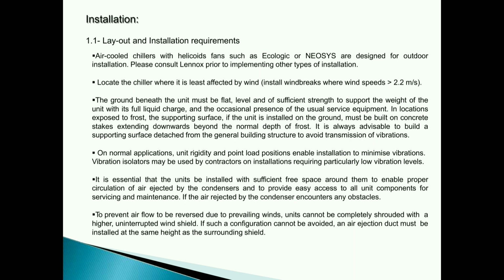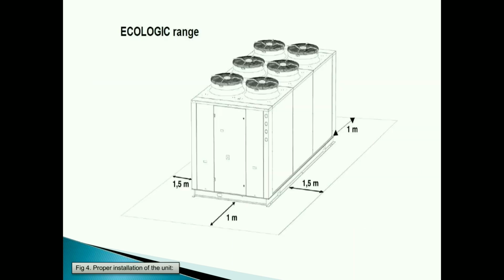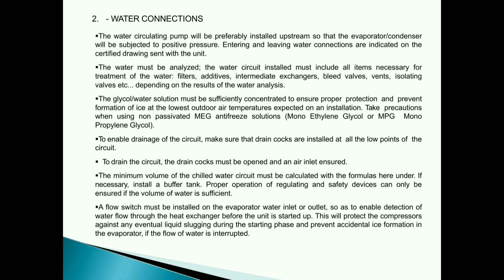It is essential that the units be installed with sufficient free space around them to enable proper circulation of air ejected by the condensers and to provide easy access to all unit components for servicing and maintenance. If the air rejected by the condenser encounters any obstacles, to prevent airflow from being reversed due to prevailing winds, units cannot be completely shrouded with a higher, uninterrupted windshield. If such a configuration cannot be avoided, an air ejection duct must be installed at the same height as the surrounding shield. Fig. 4. Proper installation of the unit.